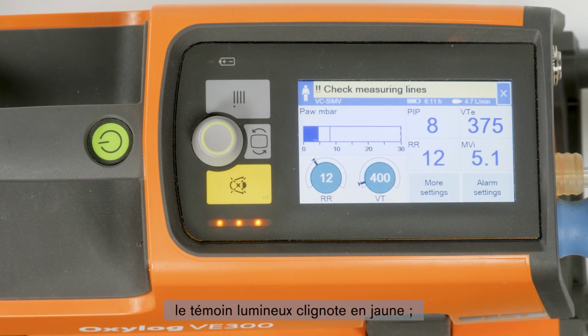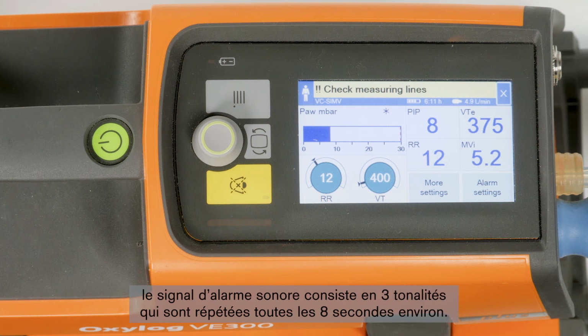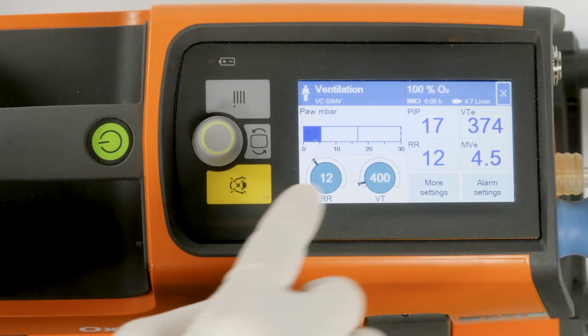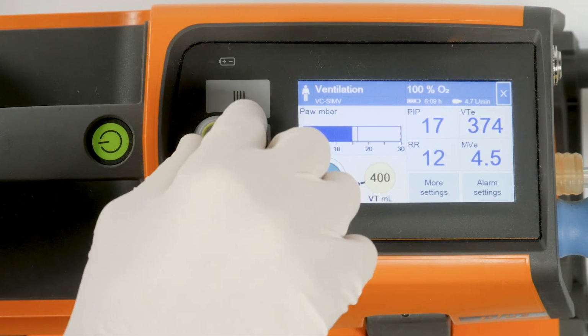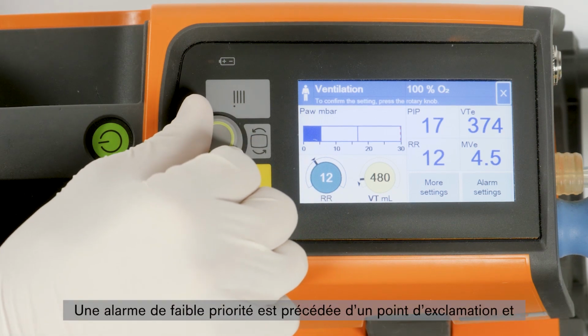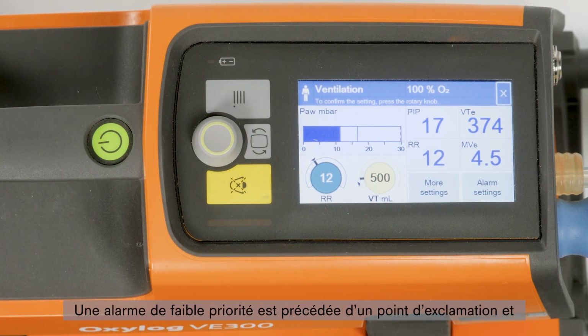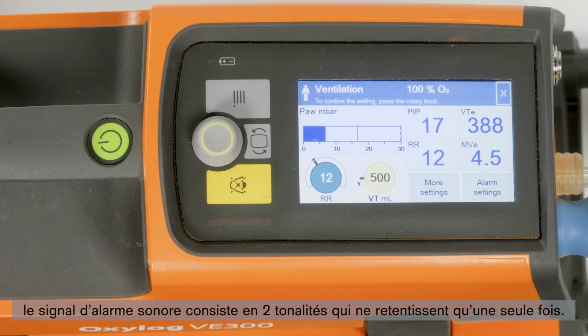The alarm indicator flashes yellow. The acoustic alarm consists of 3 tones, repeated about every 8 seconds. A low priority alarm is highlighted by 1 prefixed exclamation mark. The acoustic alarm signal consists of 2 tones, sounded only once.